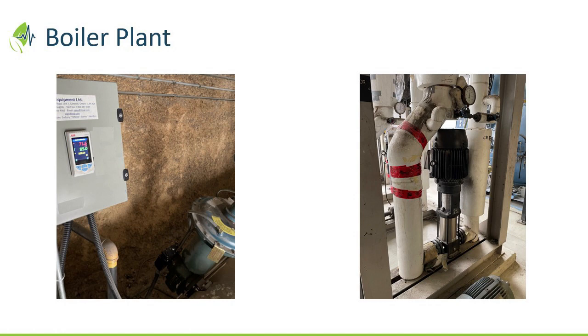Because you can recover enough heat energy that if you restrict flow, it'll actually flash the steam in the economizer and it'll fail, cause problems. So every one of these economizers and feed water pumps are installed with a fixed orifice bypass. So you're always bleeding a little bit of flow back to your feed tank deaerator. So there's two purposes for those orifices. One is to protect the pump from deadheading. So if your boiler stops calling for water, that flow's got to go somewhere or you destroy the pump. So you've always got a trickle back of water on those orifices.